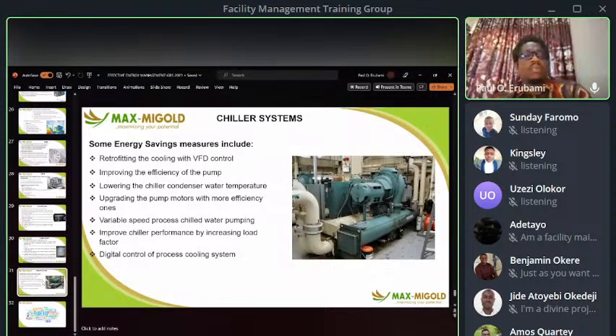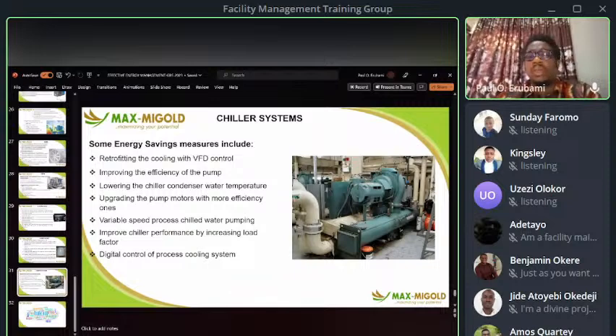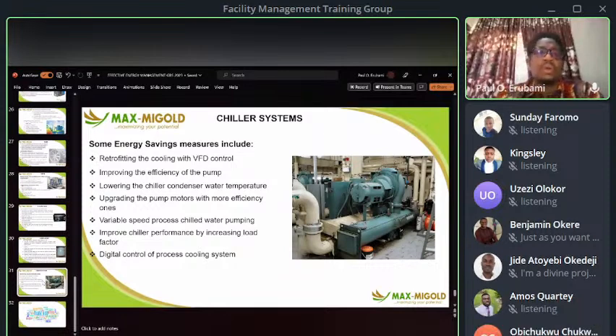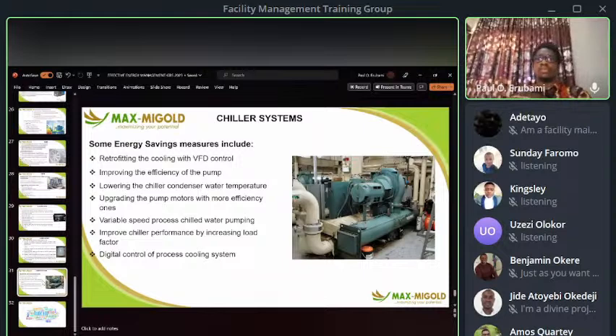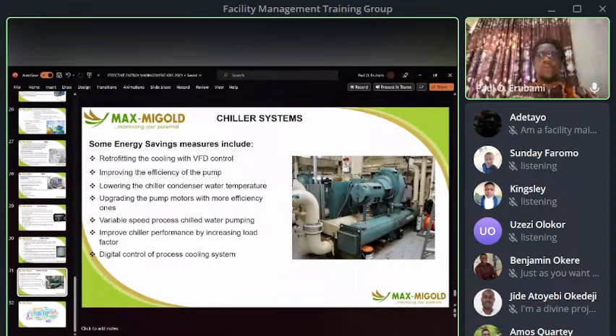Your chiller systems: retrofit the chiller system with variable frequency drives. Many of us are beginning to install VFD systems nowadays, which are more modern, improve the efficiency of the pump, and lower the chiller condenser water temperature. So usually you use the refrigerant to chill the water in the chiller, and you run that water into an air handling unit that is blowing the air that is moved in. The air gets cooled and is moved in to get circulated within your spaces.